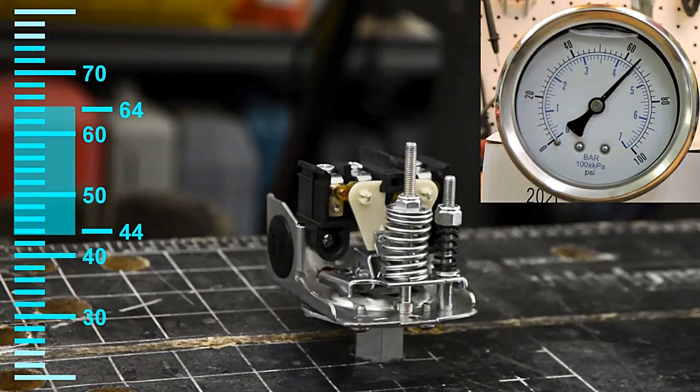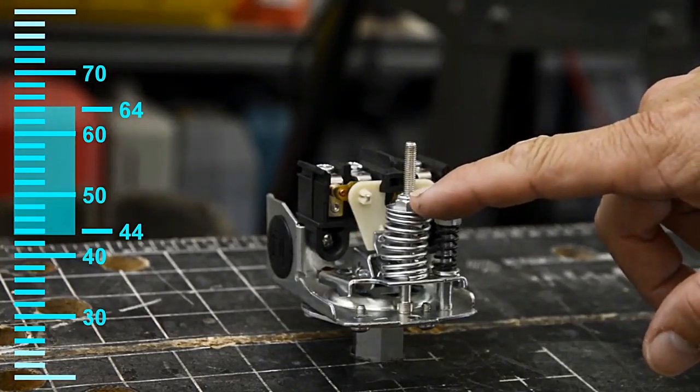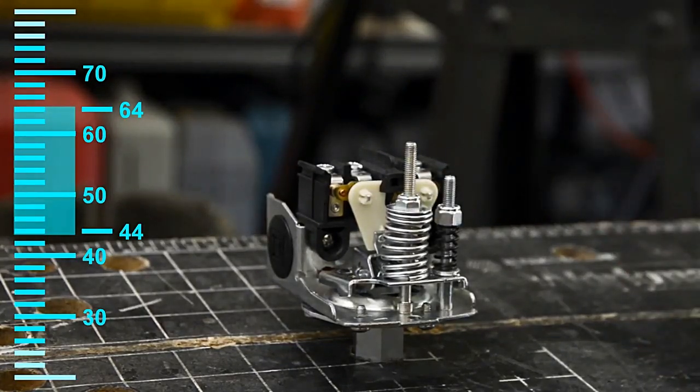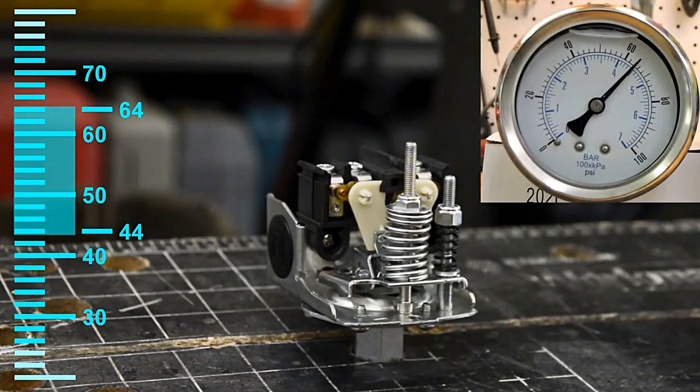And it opened at 64 PSI because I had tightened this screw down. Now I'm going to lower the pressure and you'll see the contacts close which would normally start a pump.